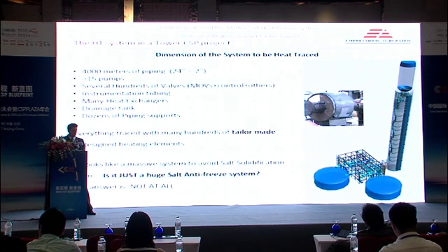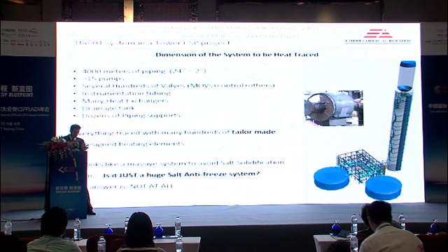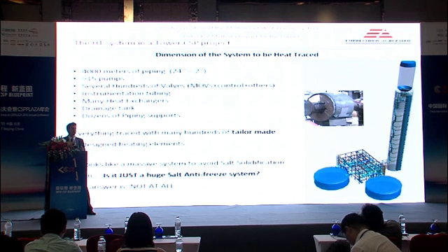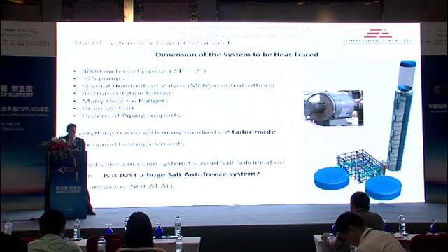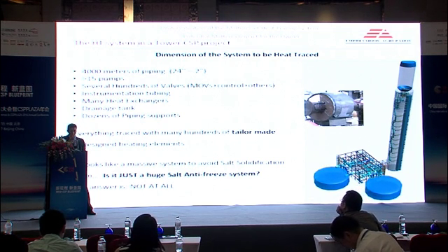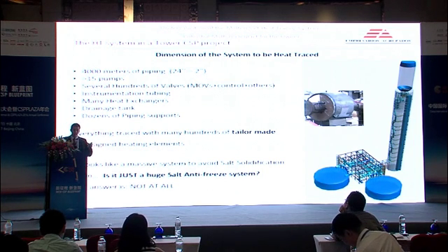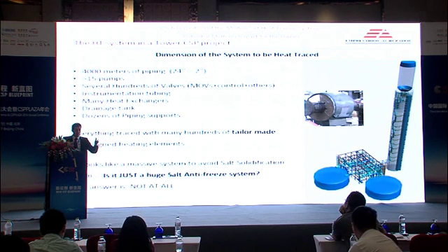If high temperatures are applied to specific areas of the equipment, it could burn something up. For example, in the bonnet of a valve, you need a different heat tracing solution or heat transfer rate, because otherwise you could burn out the gland. So it's a big problem requiring very particular, tailor-made designs, and every tailor-made area will probably have many heating elements.